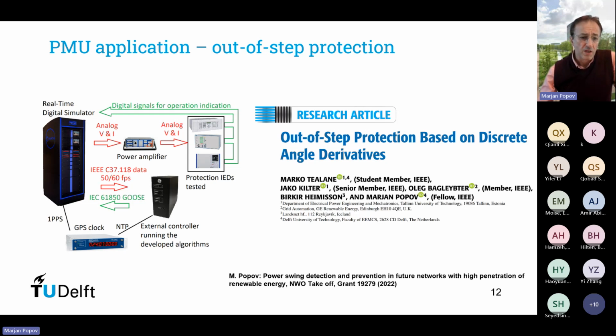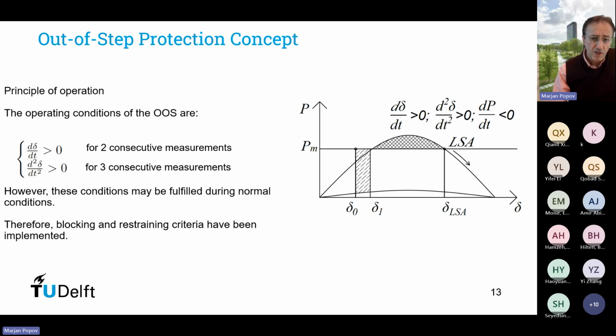What we can also see here is another system. So we have simultaneously compared this new algorithm with the existing ones, which are installed on commercial relays. We used General Electric and Siemens relays. And we provide a comparison of the results based on different system contingencies. More of this work can be found in this paper. So here I'm going to present just how the algorithm operates, and I will also address two cases. The out-of-step protection concept is simply realized by making use of the power angle curve.